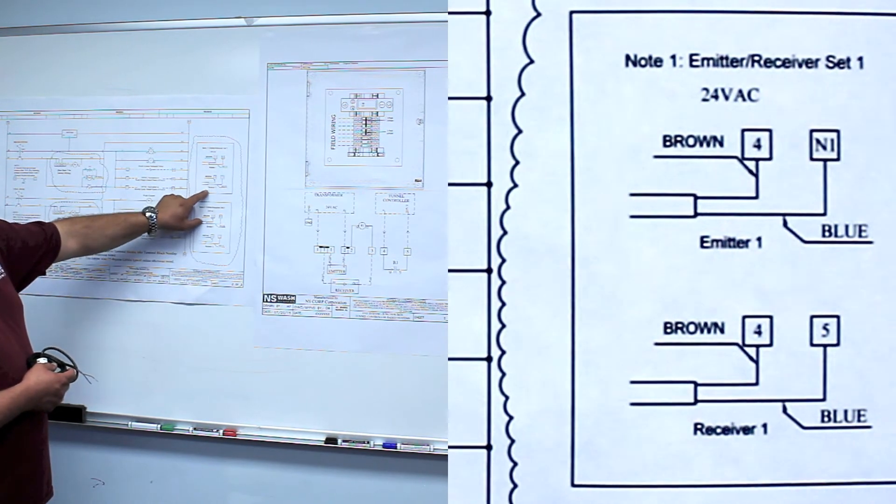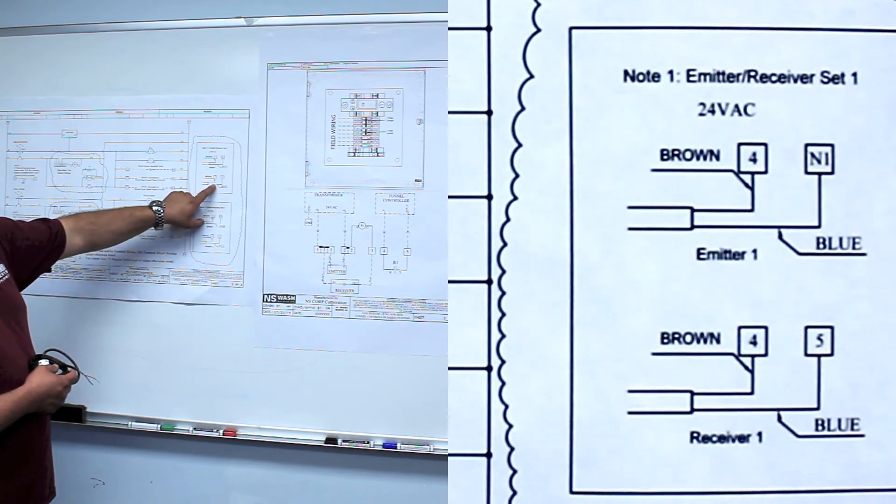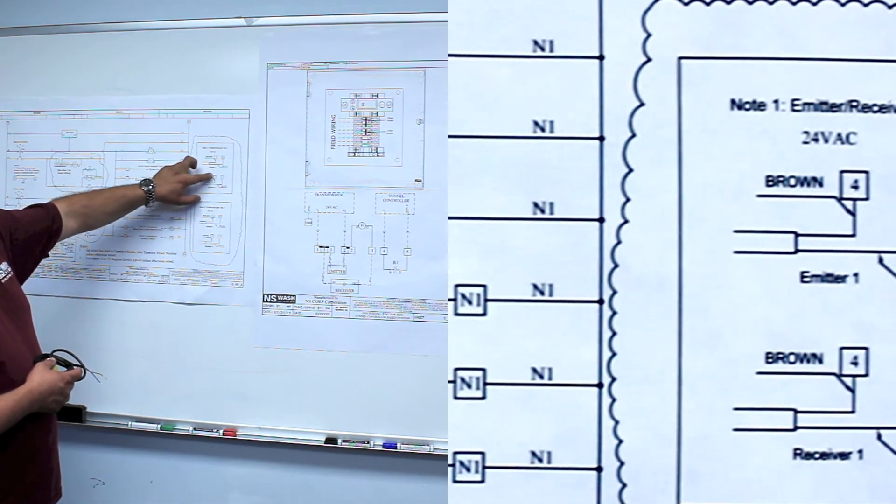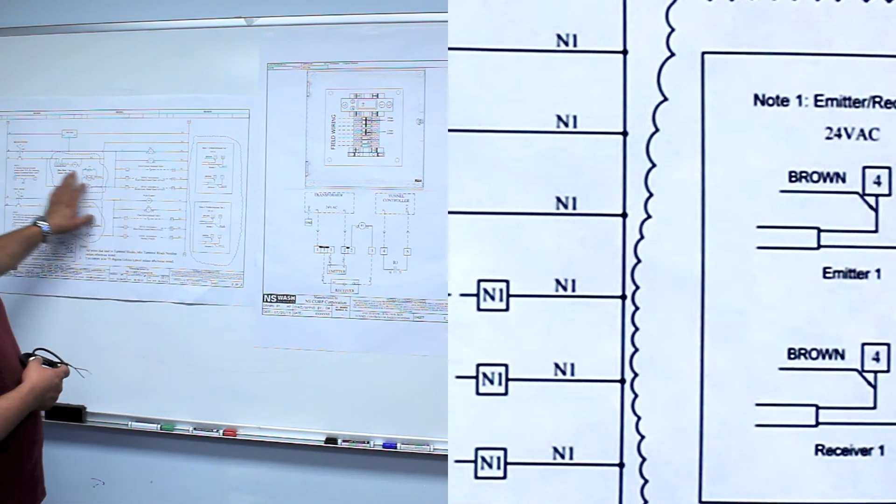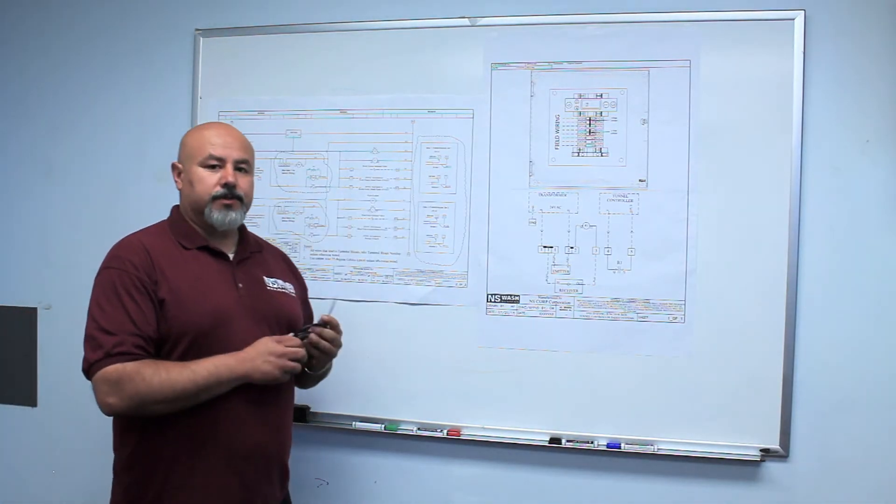Now, your receiver, brown wire goes to terminal four, and the blue wire goes to terminal five. As it's stated here, number four is the hot side of this control panel. So the brown wires always go to hot.